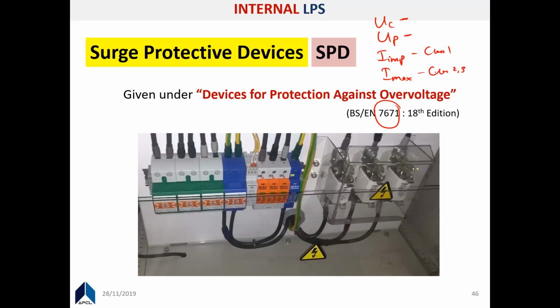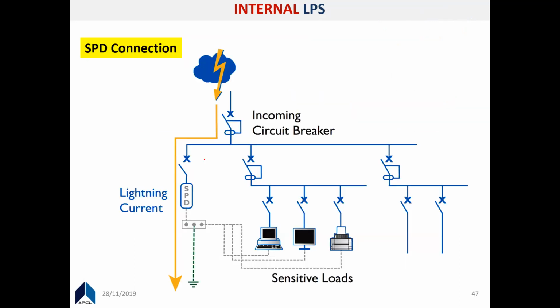So you have to select them according to the application, right? The Uc value is usually 1.1 times your phase voltage if you have individual SPDs for phases. This 10% is the system maximum that the voltage could rise to, okay? And Up is to be decided depending on the equipment connected. If you have quite sensitive equipment, then you need an Up of less than 1.5 kilovolts. But when you have higher withstand voltages, you can increase this. Throughout the installation you also have SPDs, not only at one particular connection.